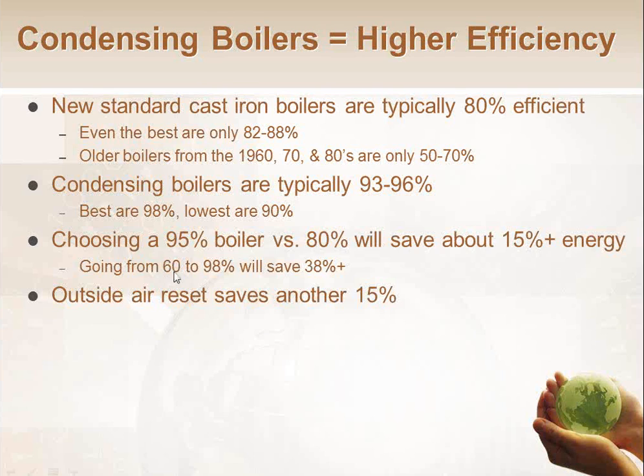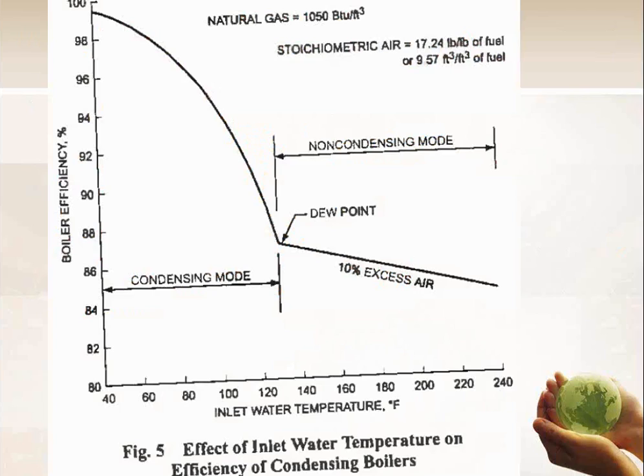If I go for something really bad, a 60% boiler, up to the best on the market, 98, 99%, I'm going to save 35, 40% of my energy. Additionally, if I add outside air reset controls to a system that didn't have it previously, I'm going to get another 10 to 15% savings out of it. And this will help explain why that is.